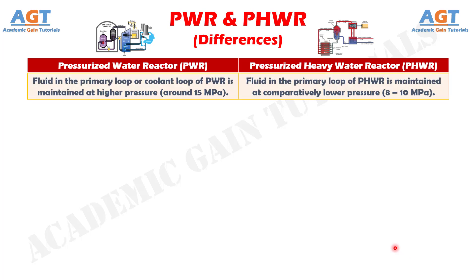Difference number 6. The fluid in the primary loop or coolant loop of a pressurized water reactor is maintained at higher pressure, around 15 MPa. Whereas, the fluid in the primary loop of a pressurized heavy water reactor is maintained at comparatively lower pressure, around 8–10 MPa.